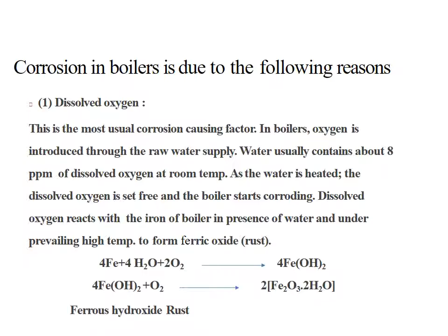Iron reacts with water in the presence of oxygen to produce ferrous hydroxide. Ferrous hydroxide upon reaction with more oxygen gives Fe2O3, ferric hydroxide, rust. Removal of dissolved oxygen. Oxygen dissolved in boiler feed water can be removed by adding hydrazine or sodium sulfite to the boiler feed water.